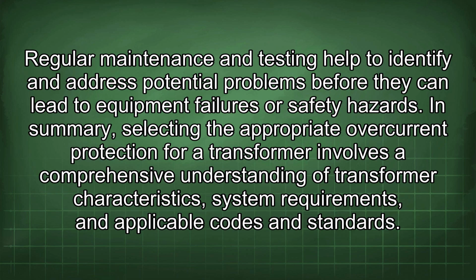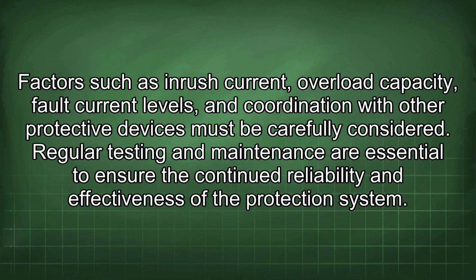Regular maintenance and testing help to identify and address potential problems before they can lead to equipment failures or safety hazards. In summary, selecting the appropriate overcurrent protection for a transformer involves a comprehensive understanding of transformer characteristics, system requirements, and applicable codes and standards. Factors such as inrush current, overload capacity, fault current levels, and coordination with other protective devices must be carefully considered.